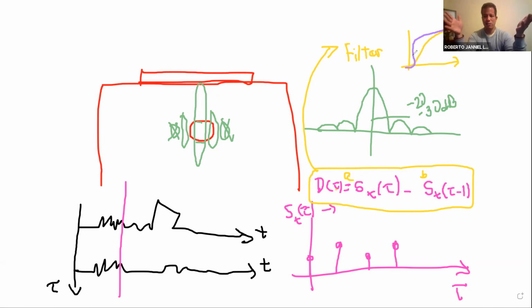That's probably the highest that you would see, like 16 firings in an ensemble. Like 10, 11, 12 would probably be the ballpark of the high number that most people would use, in the sense that it would be a good trade-off away from just having 2, which nobody would use ever, and getting into the high end of what you could reasonably do while preserving a good frame rate and being able to visualize the blood flow in the human cardiovascular system. So that would be the long version of me saying up to 16, okay? But hopefully that clarifies the answer a little bit more.